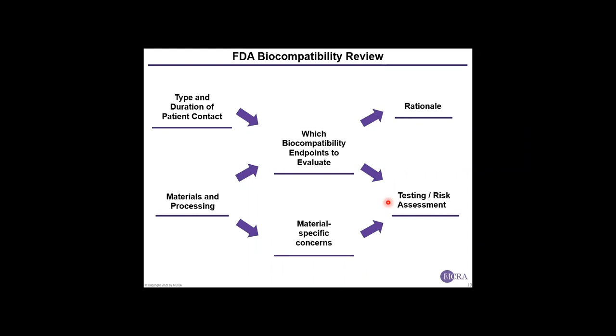So as might be clear just from the flow chart, the direction of the arrows here, device materials play a pretty prominent role in driving the biocompatibility review of a medical device. So I've highlighted in blue text some of the things that materials can determine in that review. So one of the things they can impact are the biocompatibility endpoints that need to be evaluated. So I had mentioned before that some biocompatibility endpoints are not commonly evaluated, yet are listed in the standard. So material choice can potentially drive your regulators to ask about those biocompatibility endpoints. And basically, they'll be doing that in a for-cause manner, which is why, just for the sake of this talk, I'm calling those endpoints for-cause endpoints.